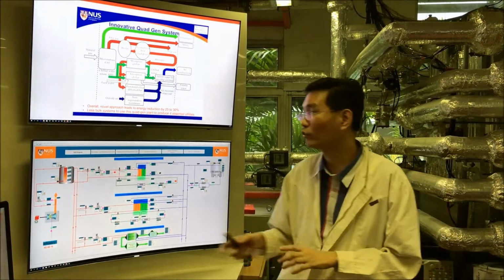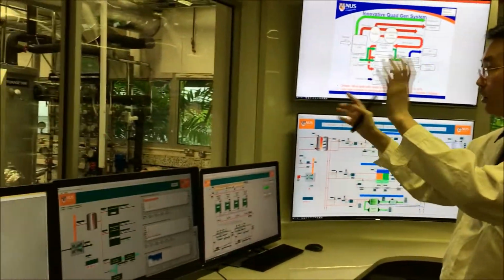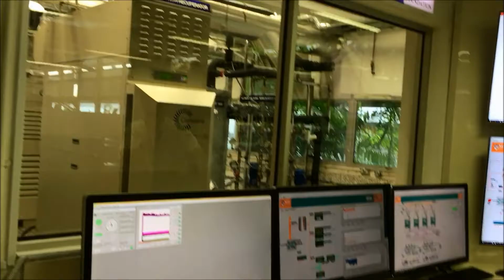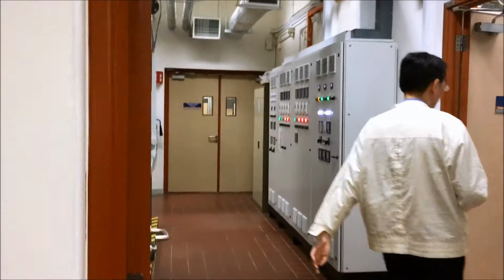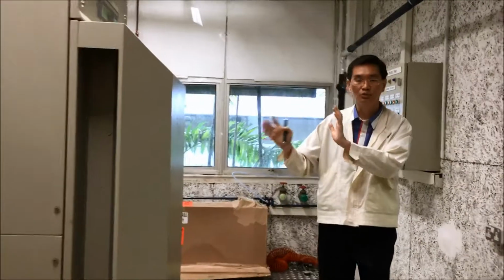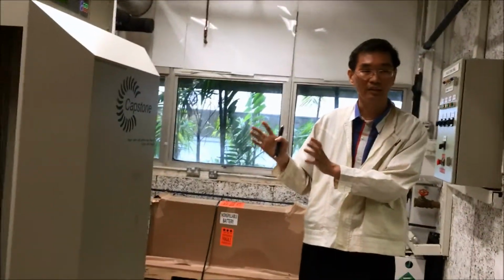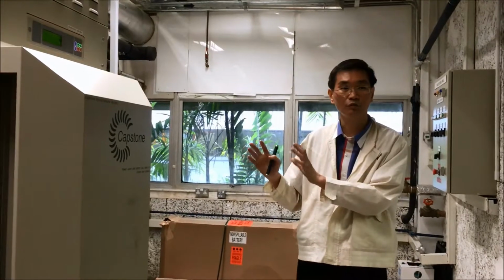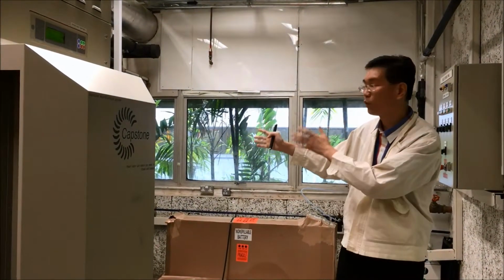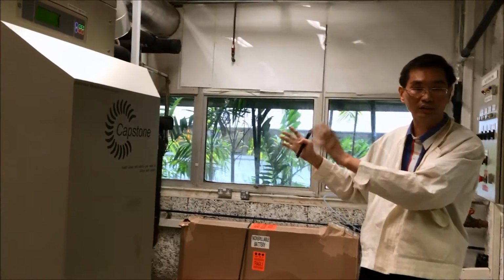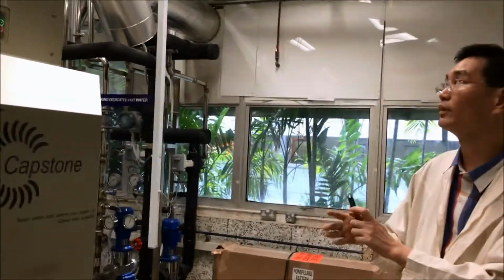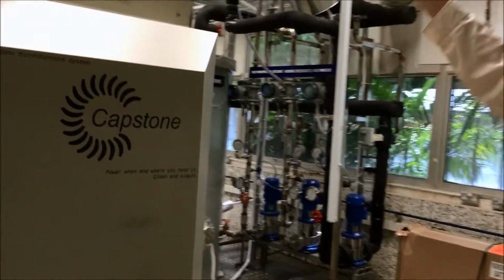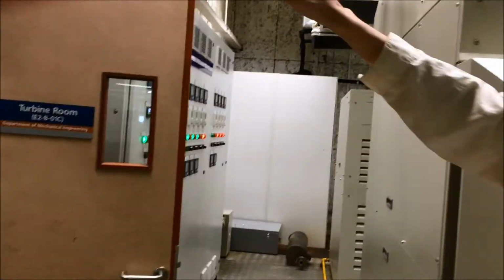Okay, next we will have a quick overview of the plant room. Here we can see from this direction we have the turbine. Right, let's go to the turbine room. Here in the turbine room, these 2 turbines will produce the electricity that we need, each about 50 to 55 kilowatt worth of electricity. We have the hot water storage system there. We can store either hot water or steam in that system here. Then the waste heat from the turbine will be harvested and piped to the other side, which comprises all the key innovations that have been developed at NUS.